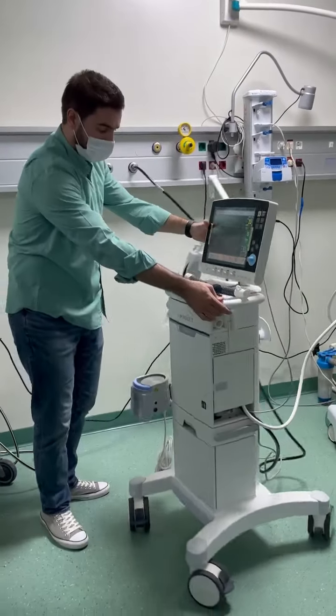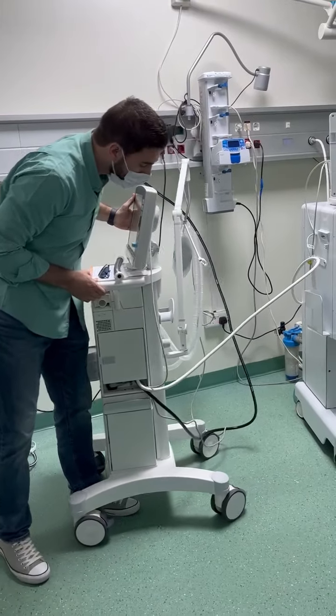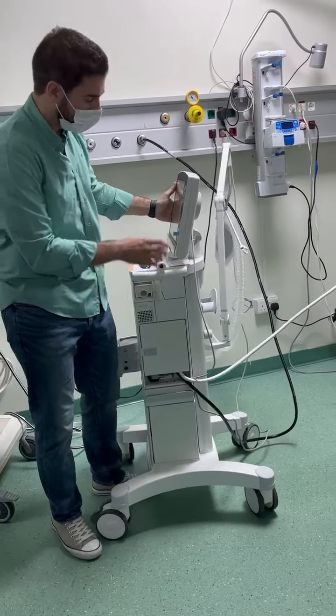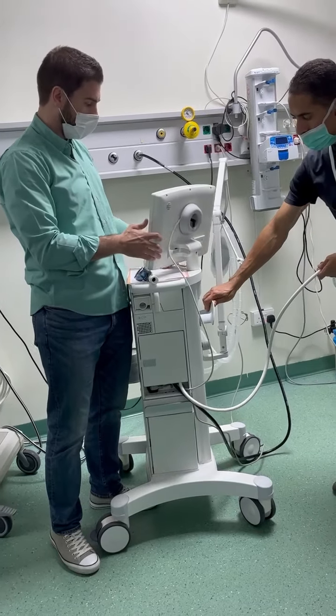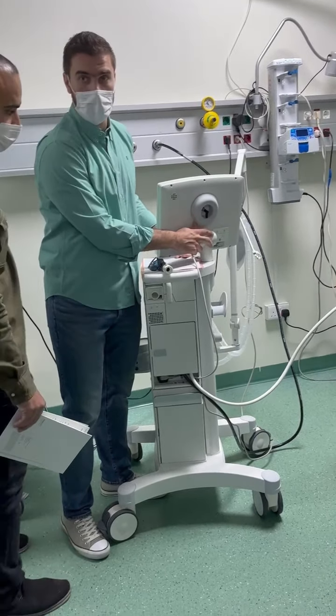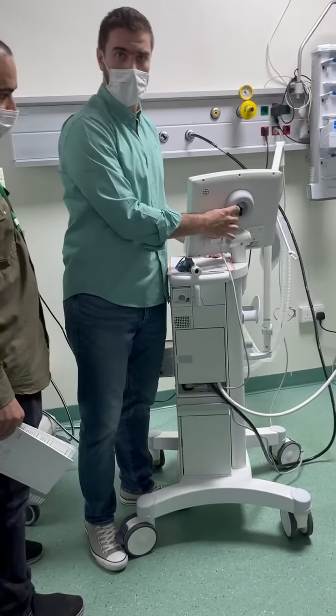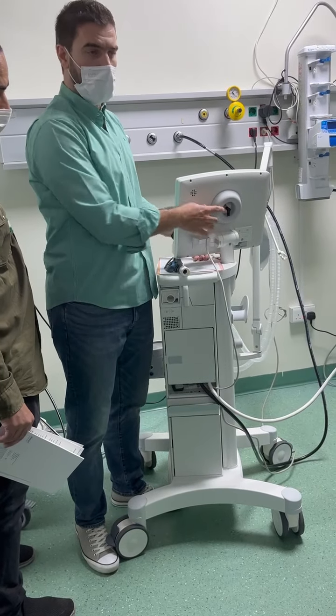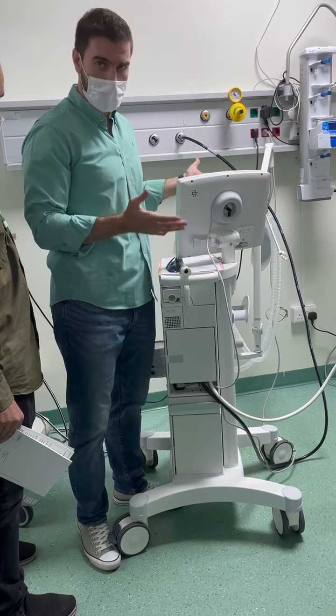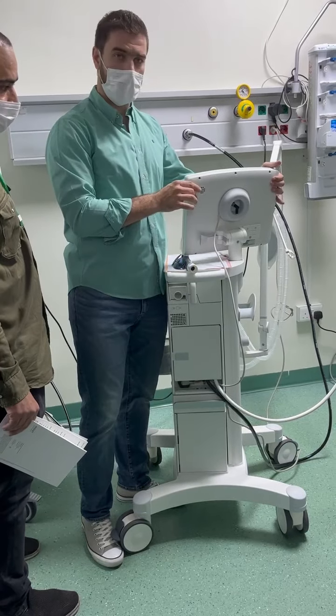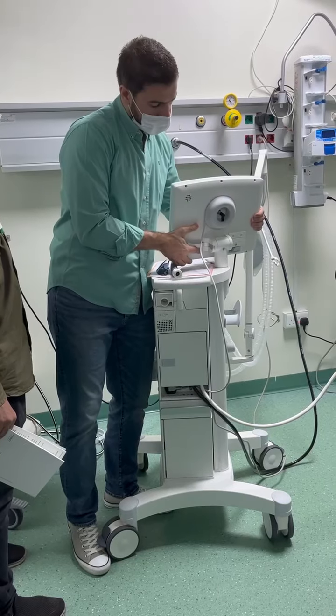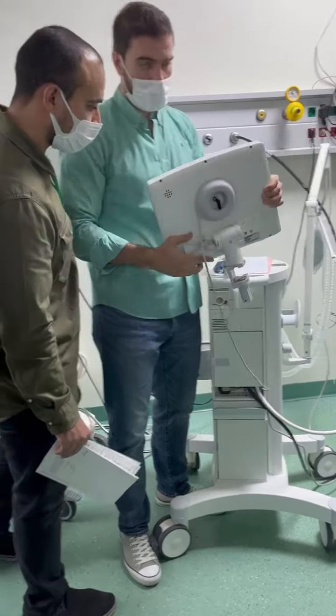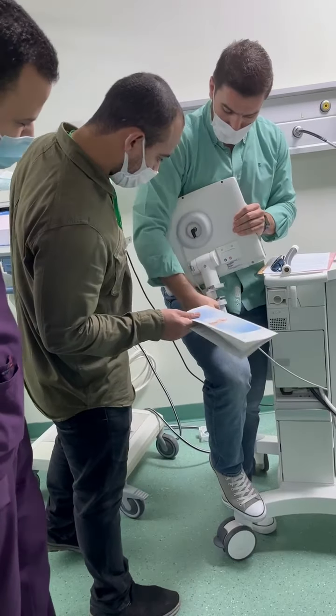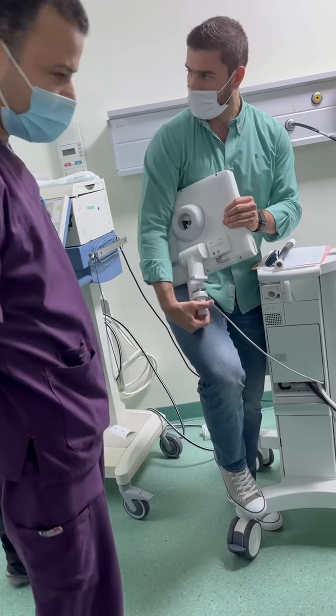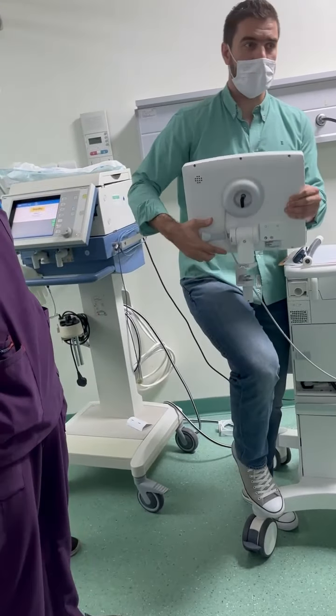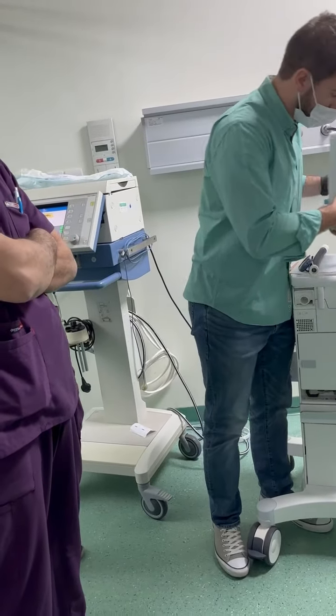This is only the screen. The screen, as I said, has a control cable from behind. This is called the control cable. The control cable is around 3 meters, 2.8 to be exact. What is the benefit of this one? In some cases, if you need to take out the screen and put it outside, very simple. Just take it out. You can put it on any table. In an isolation room, it's very useful too.